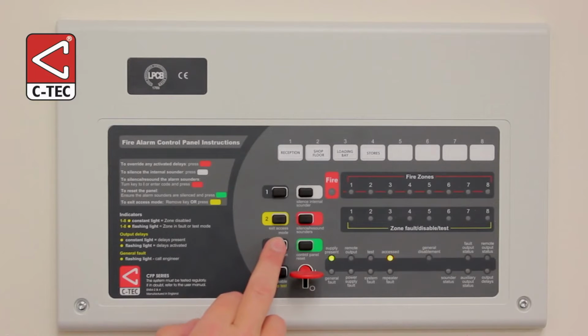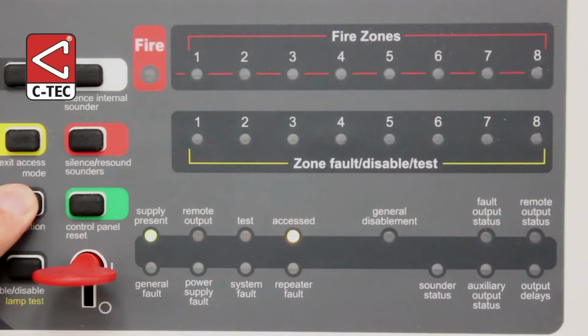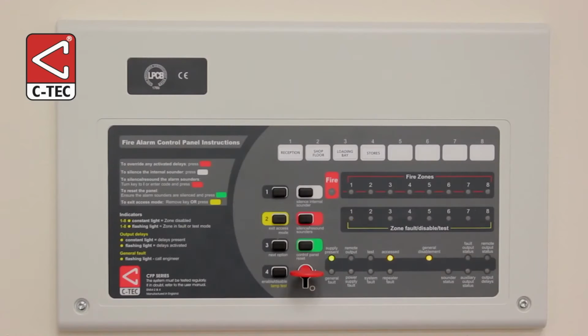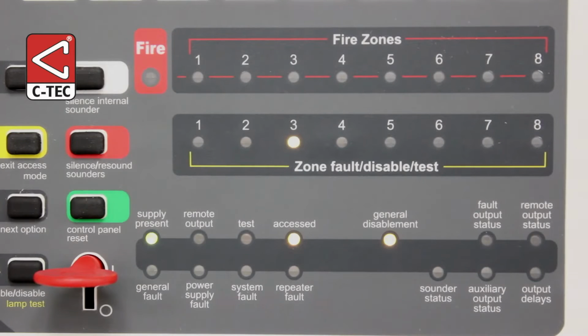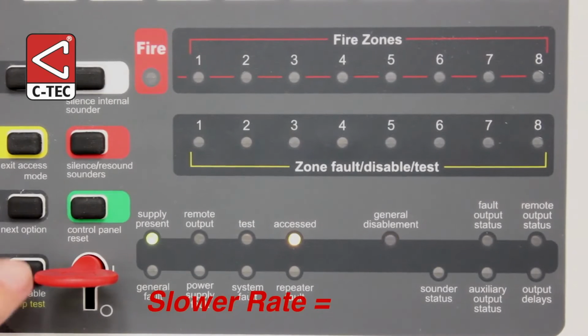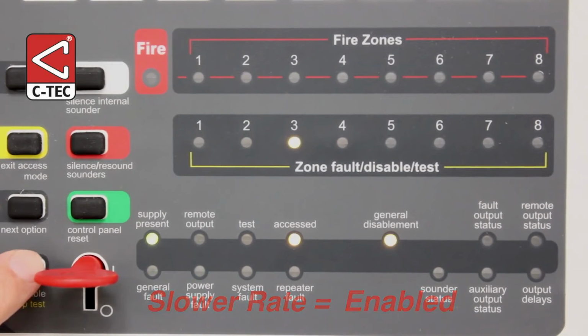To start the process, press and hold the Next Option button for 3 seconds until the General Disablement and Zone 1 Fault lights are flashing yellow. For the purpose of this video, we'll use Zone 3 as an example of a zone that needs disabling. Press the Next Option button until Zone 3 is flashing. If it flashes slower than the General Disablement light, its current status is enabled. If it flashes at the same rate, its status is disabled.